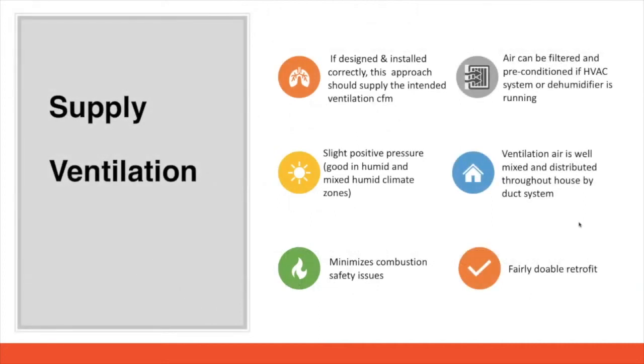Supply ventilation is what our ventilating dehumidifiers provide. If installed and designed correctly, it should provide the intended ventilation that you're looking for, which of course means we need our ductwork for that ventilation pulled tight. Not a lot of runs, not a long run or continuous bends in it, but we should be able to get that desired ventilation CFM that we're after with supply ventilation. Again, we're going to do that slight positive pressure, which is really good in a humid and mixed humid climate to try to stop that infiltration. It minimizes combustion safety issues. Now, the air that you're bringing in can be filtered through our dehumidifier. We have a MERV 13 filter. Now, if the dehumidifier is running at the time that we're bringing in outdoor air, we can remove a little bit of moisture from that.